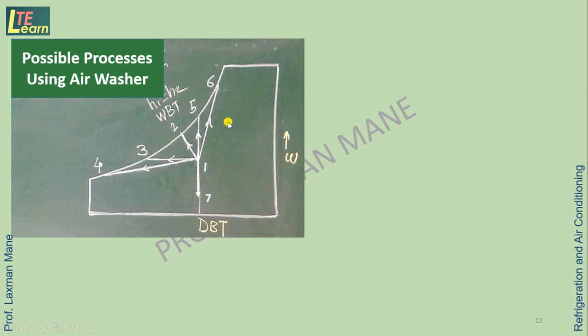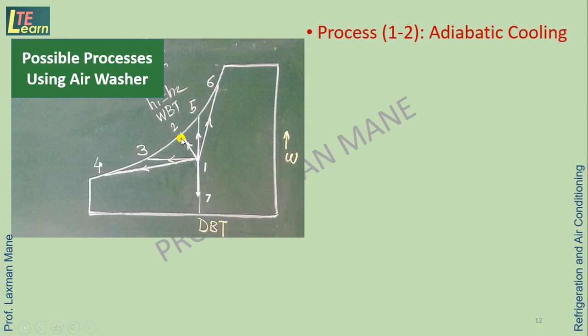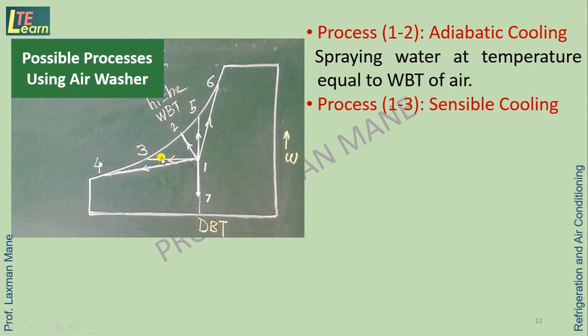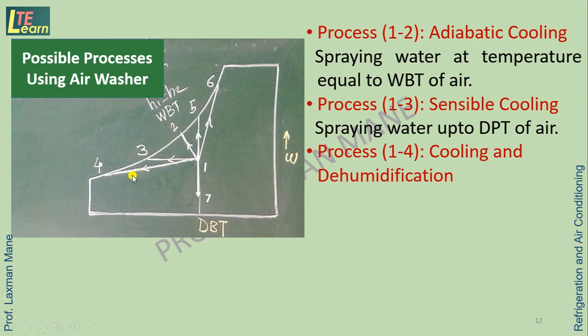The possible processes with the help of an air washer are: Process 1 to 2 — adiabatic cooling — occurs when water is sprayed at a temperature equal to the wet bulb temperature of the entering air; there is no change in enthalpy (H1 = H2). Process 1 to 3 — sensible cooling — is possible by spraying water up to the dew point temperature of air. Process 1 to 4 — cooling and dehumidification — is done by using water below the dew point temperature of air.